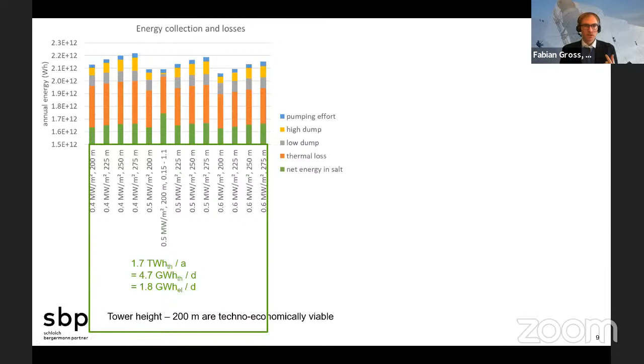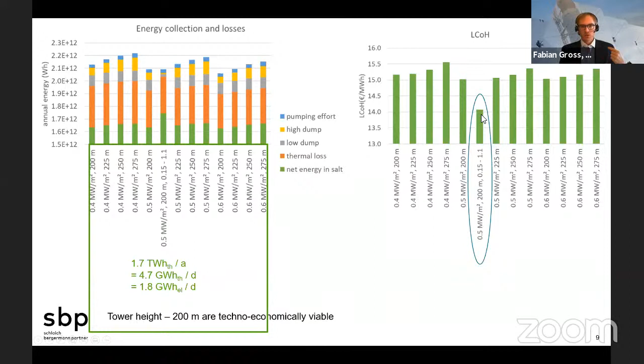Therefore, we developed this special solution that reduced the cut-in to reduce load dump and allowed for overcharging of the receiver, while taking care of the maximum flux supplied and the limits. This leads us to proposing a relatively low tower with a medium receiver, a special pump configuration, and a good heliostat control system with the ability to go into overload.